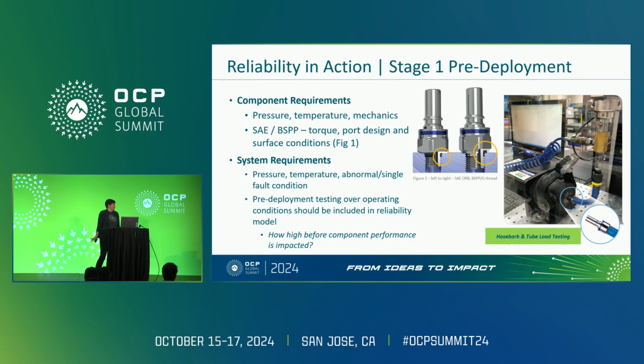Before we turn on the pump even, there's a lot of things we can do to set ourselves up for success by speccing the right components. So for QDs, obvious things like pressure, temperature, and flow ratings, but also the way that the QD actually interfaces with the rest of the system. Handmate and blindmate connections, we saw a lot of blindmate UQDs out on the floor where you might need to factor in loading from misalignment tolerances. Threaded connections, where, I think we were just talking about vibration in the IEC standard right before this talk, you want enough torque to seat the part to make it seal, but not so much torque that it's going to induce some undesirable stresses long term. Hose barbs, certainly making sure that you have not only the right tube to the right barb, but checking that that interface can stand other unintended loading scenarios like side load from large bend radii in the connected length.